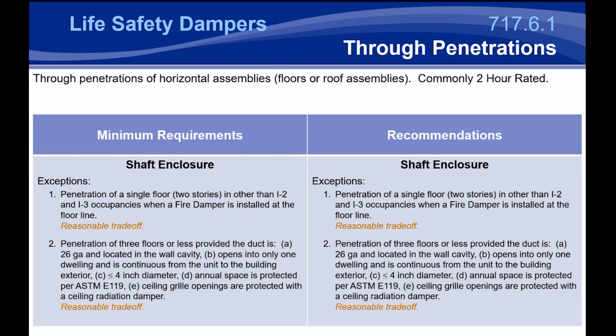Now, the biggest exception I see used that's a valid trade-off is if you've got bathroom exhaust, typically where you're protecting the ceiling membrane. It's a small diameter duct and it only opens to a single dwelling. You can certainly penetrate that, and it's 26 gauge duct, so it's fully ducted, and it's 3 floors or less. You can certainly use that without a shaft enclosure. You don't need that shaft enclosure for those. I see this used quite commonly for bathroom exhaust in hotels and things like that. It's a very valid trade-off.